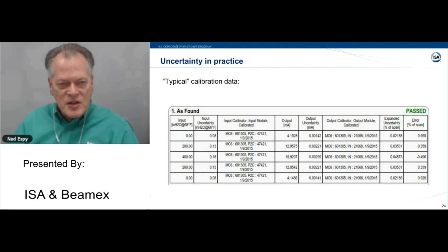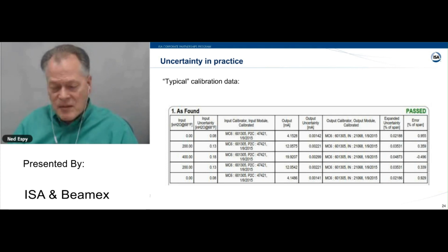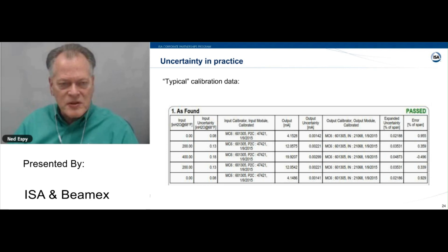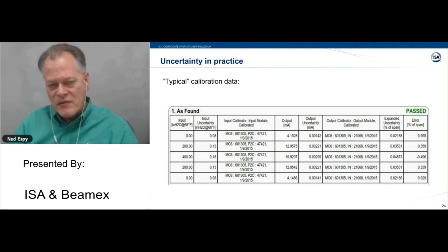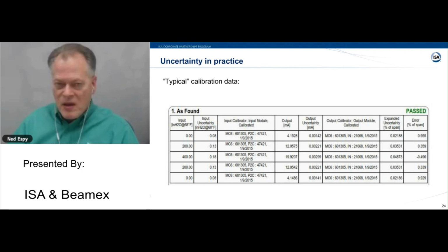So here's typical calibration data. Over on the left, there's a column for input. Then in the middle, there's the output reading. And over on the far right, it has the error as a percent of span. Those are typical things. It's also showing what was used for the input standard and what was the reference standard for the output.